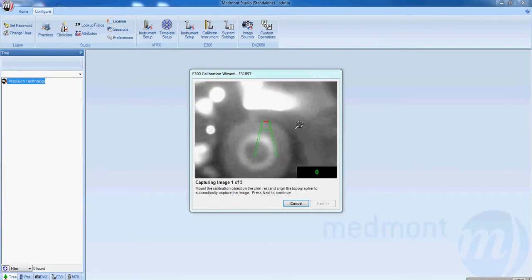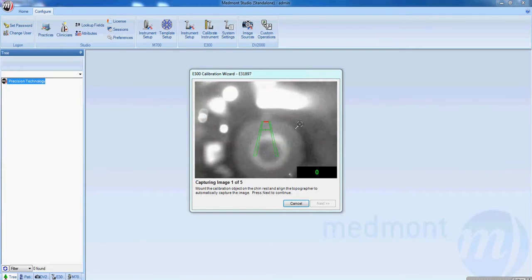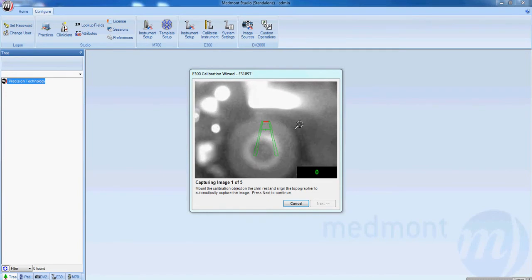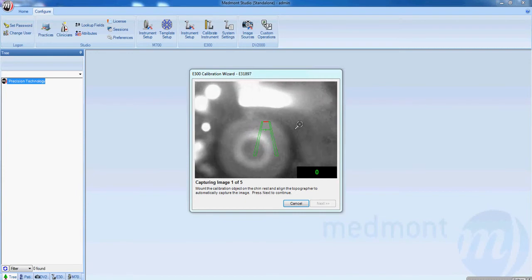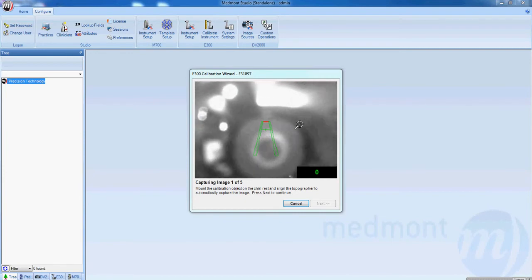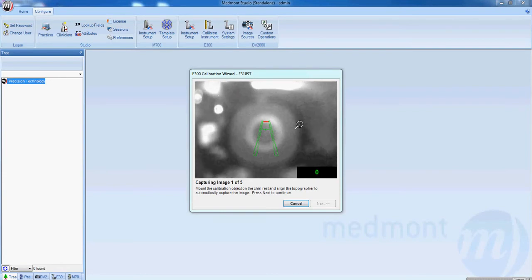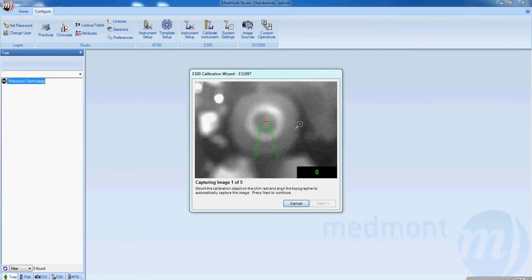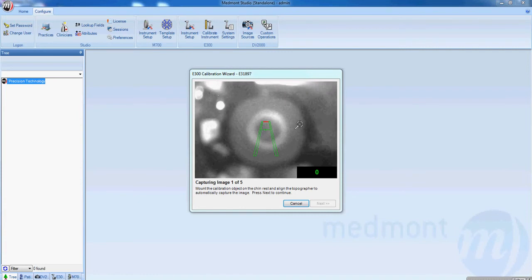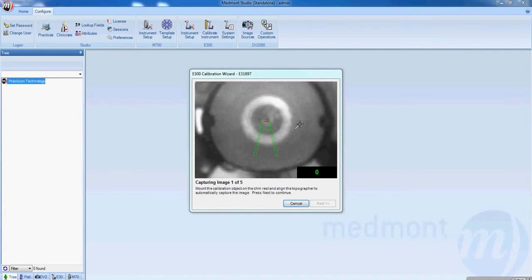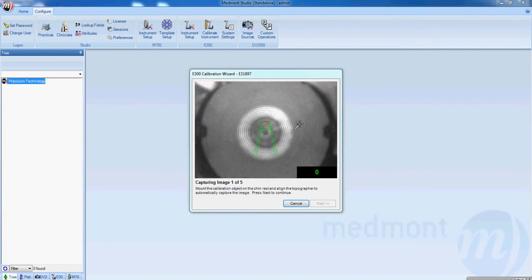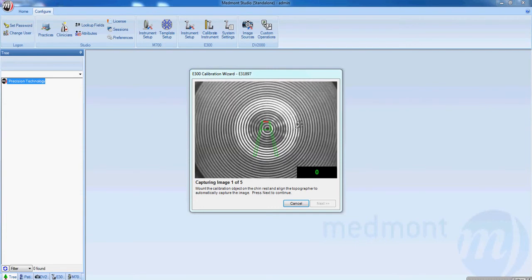Take the joystick and use it to center the instrument to the calibration ball. The instrument can be controlled laterally by moving the joystick nasal or temporal, or right or left. Then rotating the joystick, you can move the green crosshair up or down. Move the instrument forward until the rings appear more clear, parallel, and even.